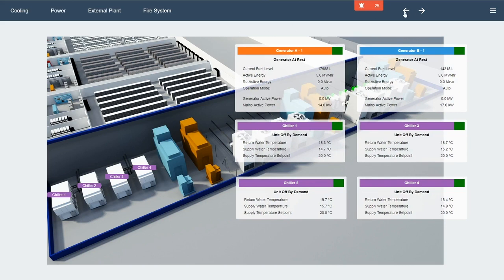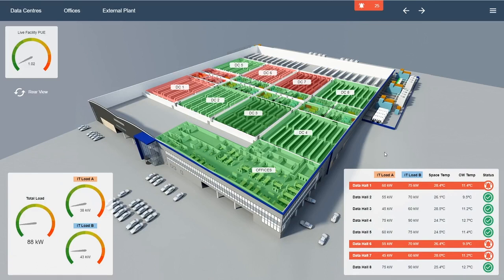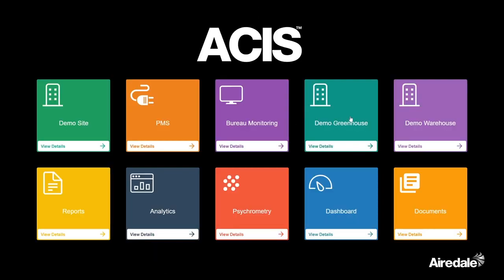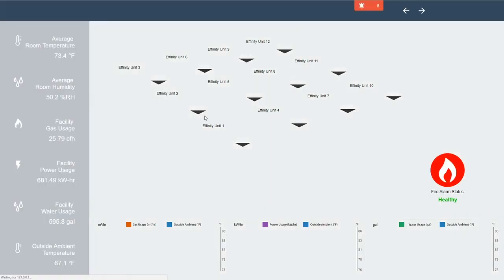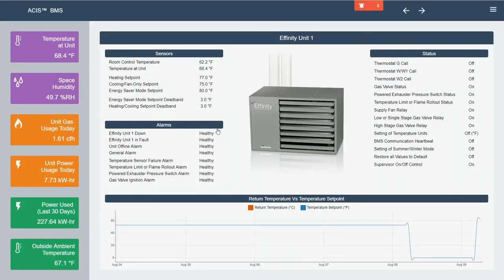There are ways of doing it. You can use thermostats, BACnet thermostats, but all that does is give you the temperature, and you can turn the unit on and off, and you can change a set point. This actually gives you an interface to the actual unit where you can see in real time what the unit's doing and the health of it, and whether the unit's running and operating exactly how you'd expect. I think this is something that is different. It's something that the market hasn't got, and I think it's something that will be very important once customers see it and get in front of them. This is something that's going to be different and be a big selling point to them.